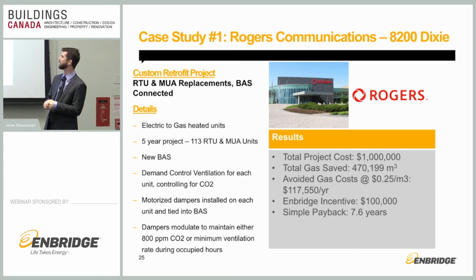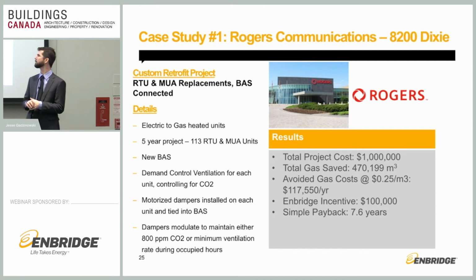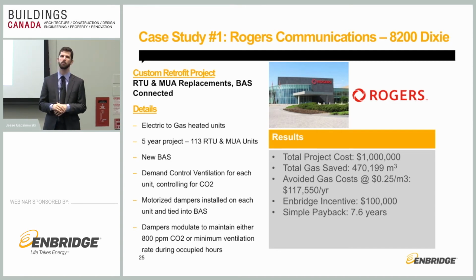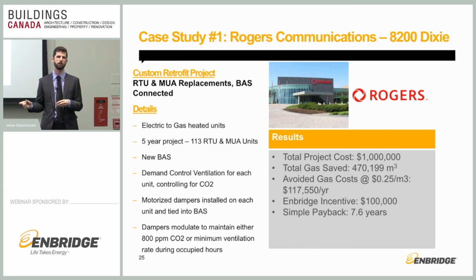And they had 113 rooftop units and a couple of makeup air units that they wanted to tie into the BAS, put it all under demand control ventilation, where the units before were single zone onboard controllers that were on thermostat settings and then a 12-hour timer.